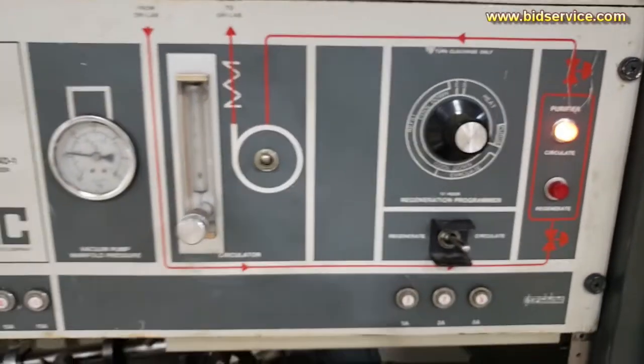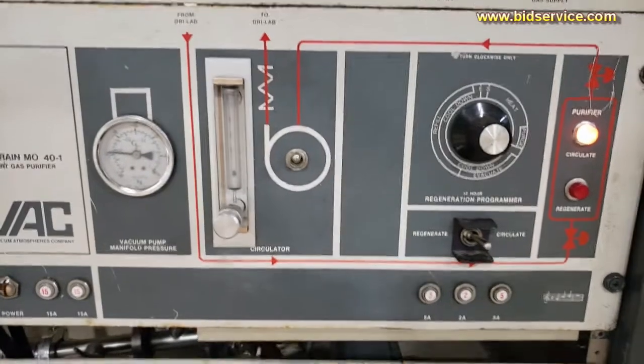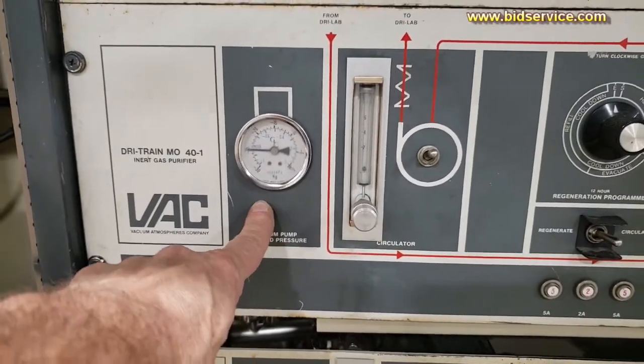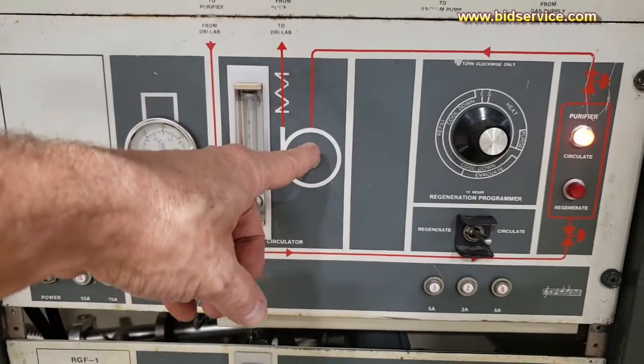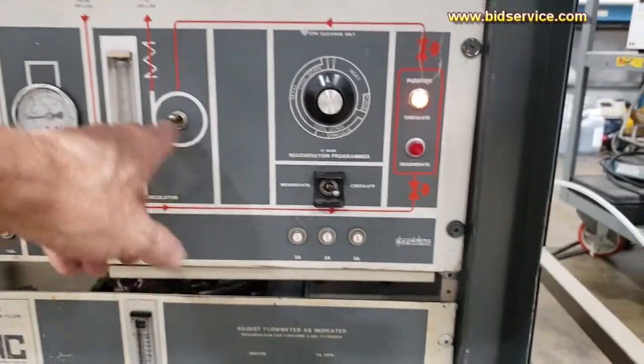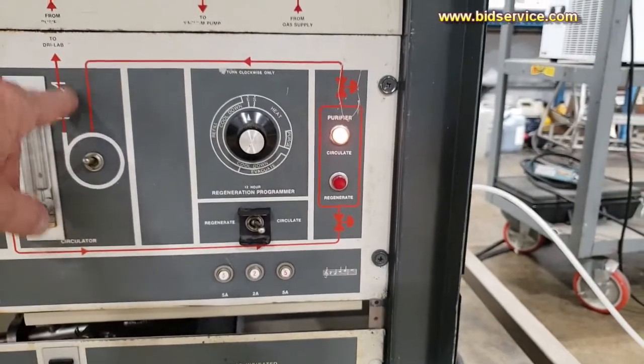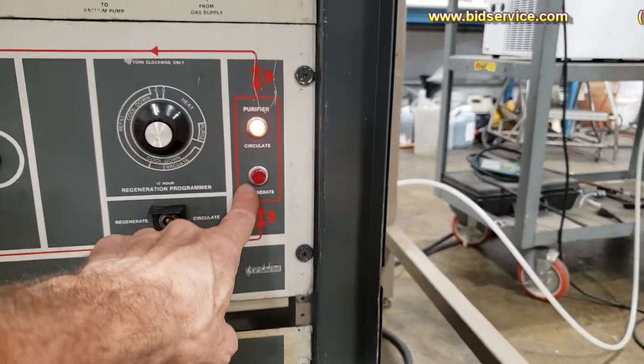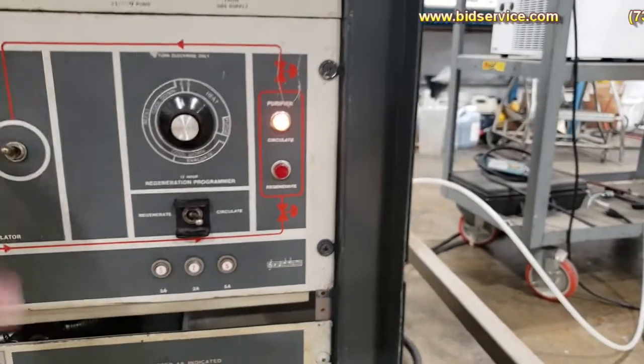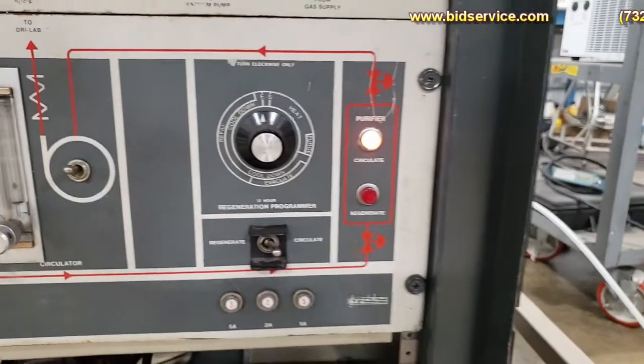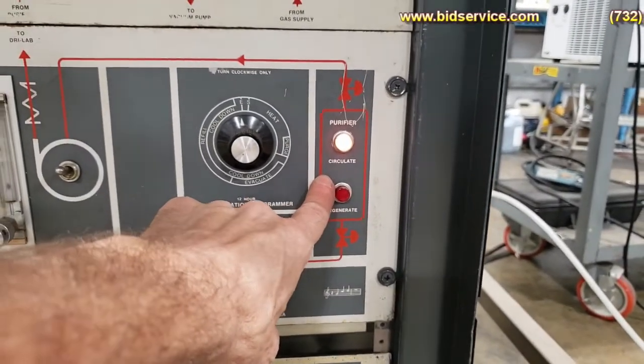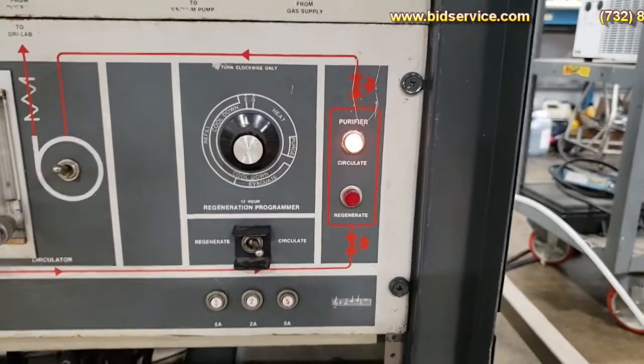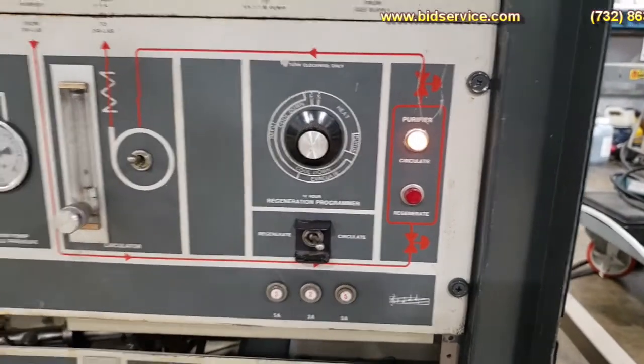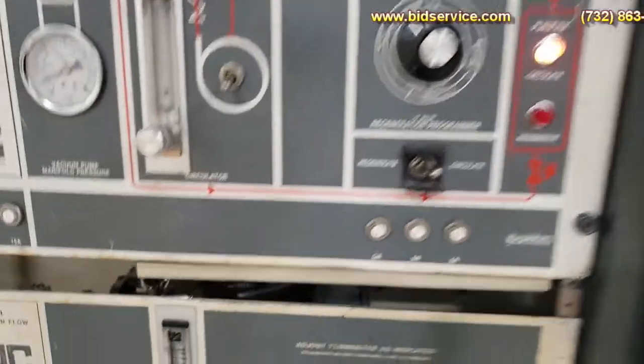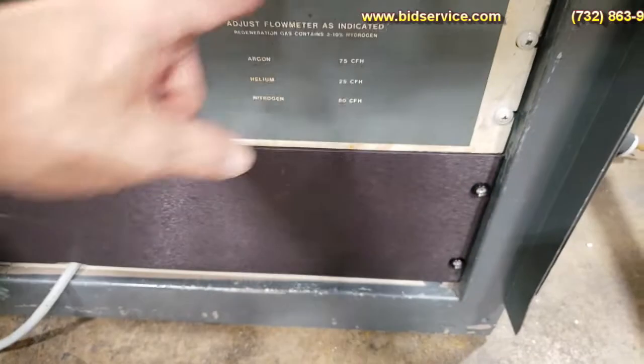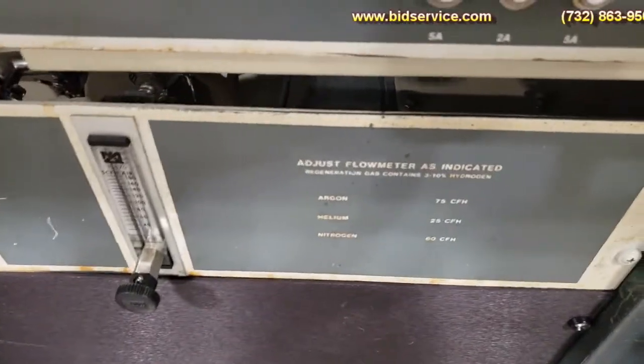Okay, while we're here, I just want to point out a few other things. Here's your vacuum pump pressure manifold gauge. This is your on-off for your circulator, which is kind of like a schematic here. It'll circulate through the box, come back through the purifier, and then return to the circulator and box. The purifier is going to remove your excess water vapor and oxygen. If you want to shut the circulator off, you hit this button here. I don't know if you can hear that, but it's winding down. There's a blower right inside here. It's circulating. It's a little hard to see.